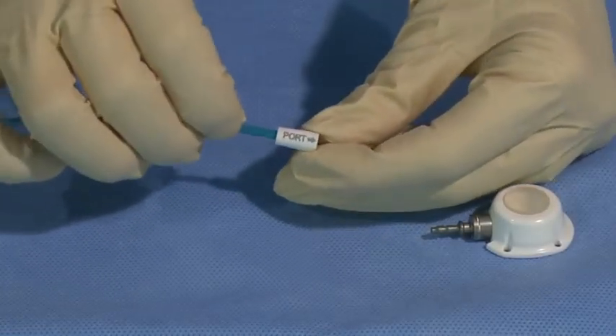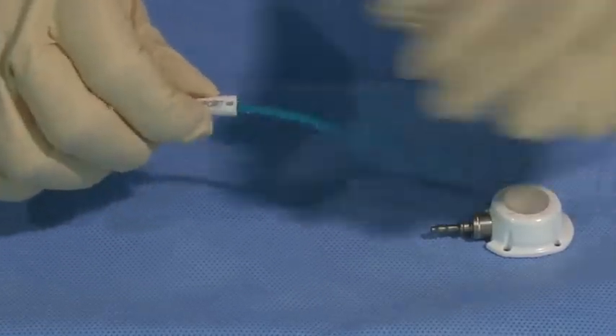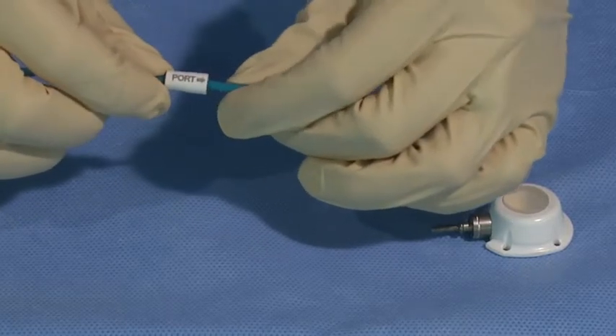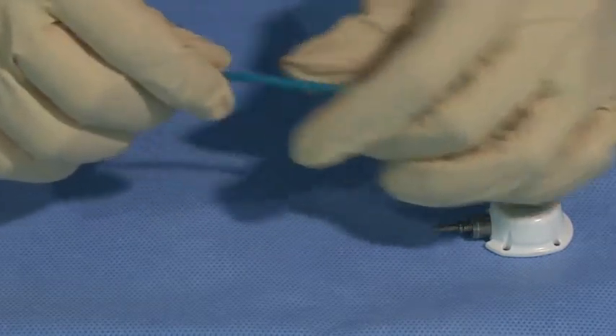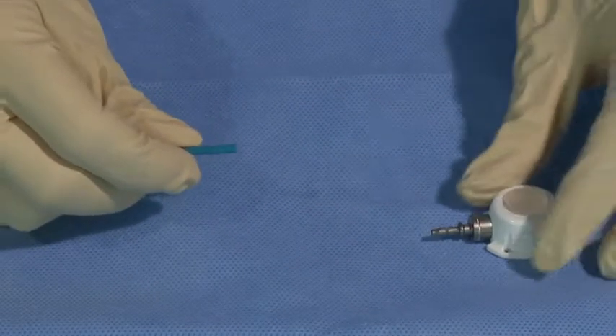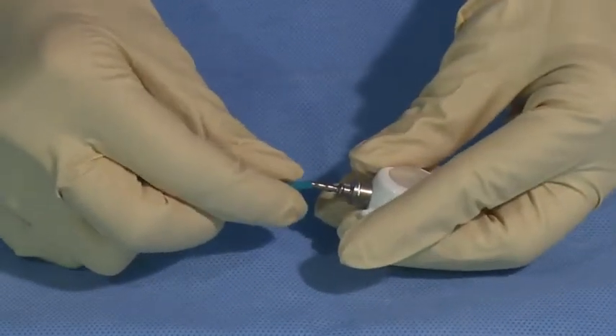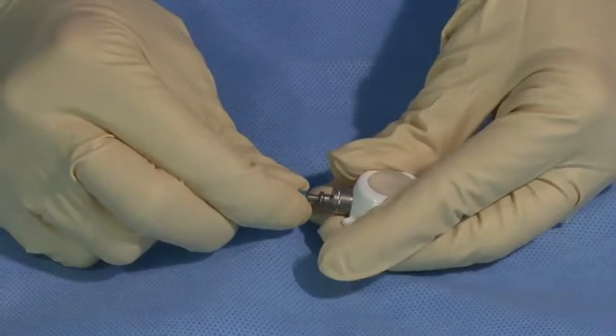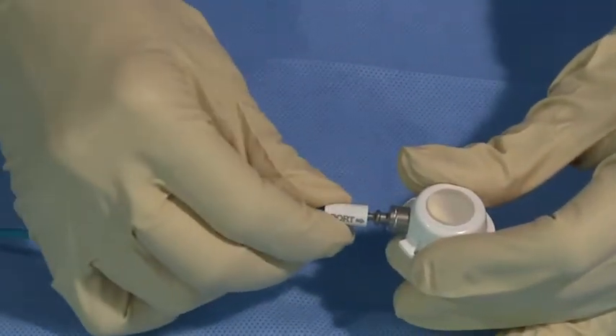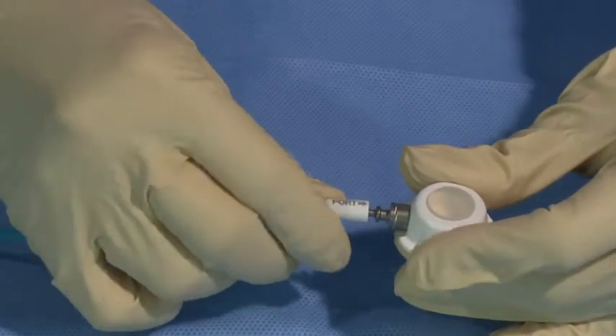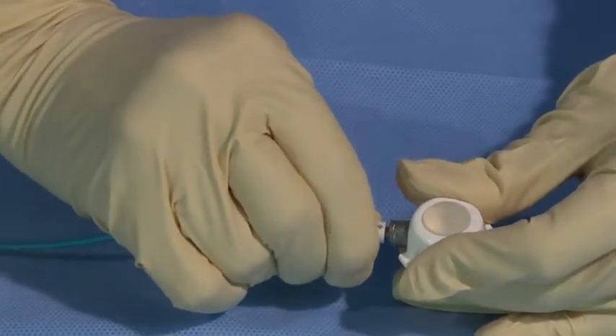Orient the snap lock connector so that the arrow marking points in the direction of the port. Advance the catheter over the port stem to the midway point, covering the first barb. Advance snap lock connector, pushing from the back of the lock until it engages with tactile and/or audible feedback.